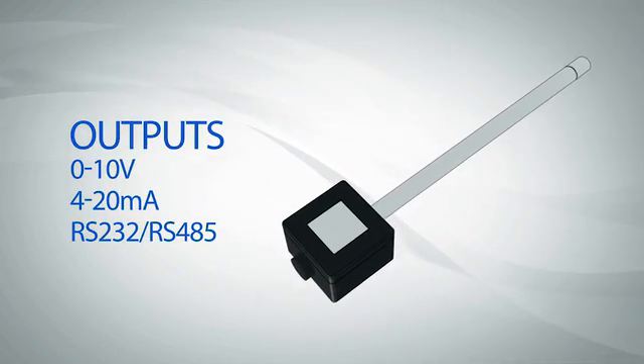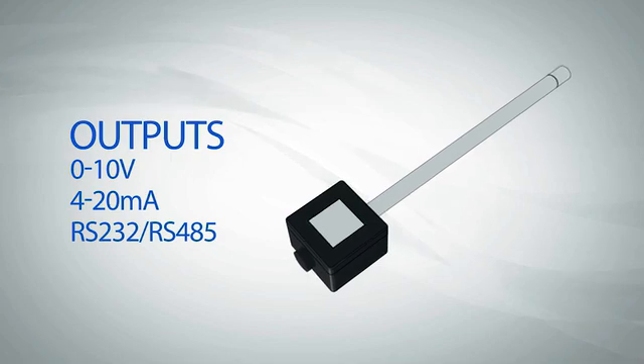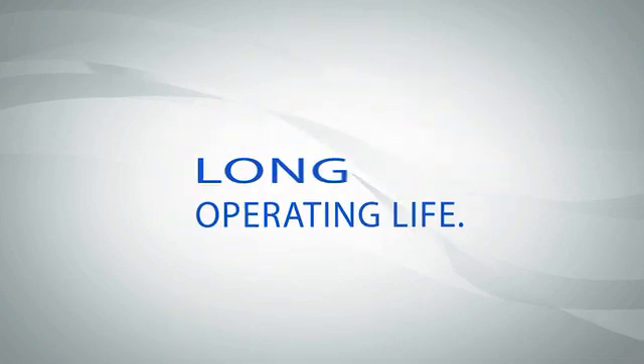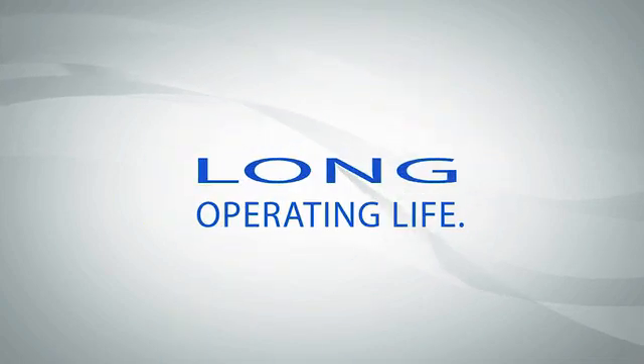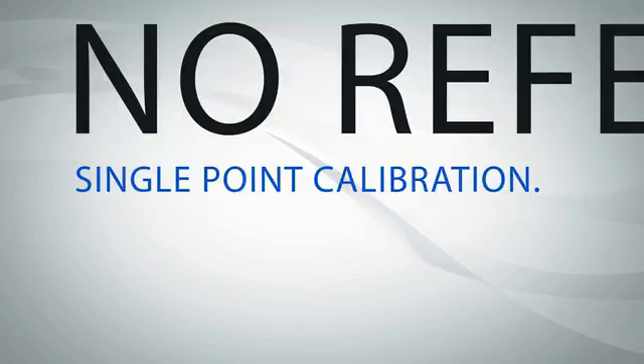The sensors come stand-alone or with integrated electronics, offering digital or analogue industry-standard outputs. Their long life comes from their non-depleting sensor cell technology. No reference gas is required, and easy single-point calibration can be performed in fresh air.